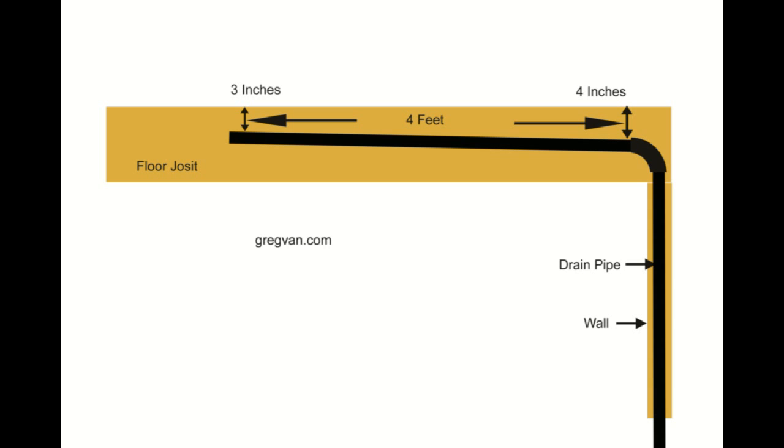If these pipes slope an eighth of an inch per foot, let's face it, they're still going to drain. They just won't meet your local building codes. Building code is a quarter inch per foot. It can always be greater, but it can't be less.